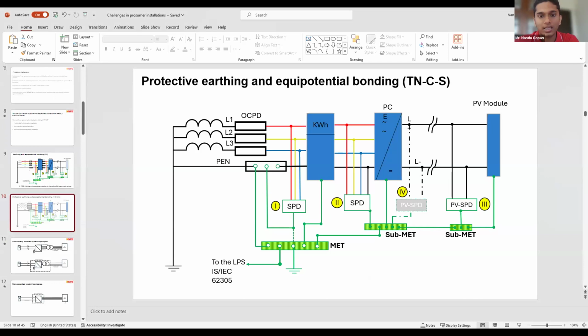Actually, in that question, you can divide it into two parts. One is the system referencing conductor. Depending on what type of topology you are supposed to use, if there is any galvanic separation, then you can or you might not do it. It depends on the topology. But the other one is the equipotential bonding. Equipotential bonding must be done. You should not have a separated thing.